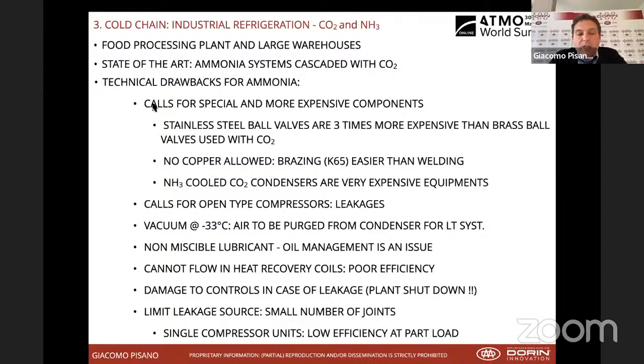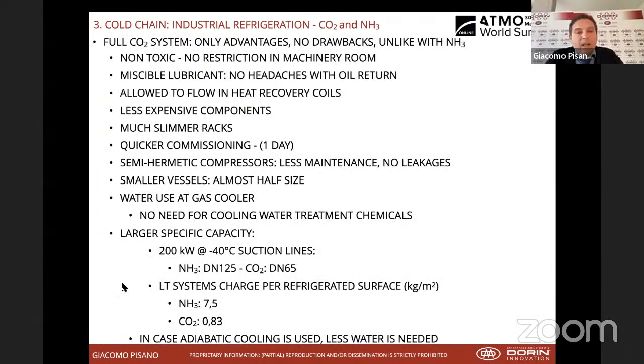During heat recovery, in most cases, ammonia cannot flow directly in heat recovery coils. So for heat recovery, CO2 may be more efficient. In case there is some leakage, you have to take care that the leakage does not affect controls. Otherwise, the plant may shut down. Clearly, in order to decrease the number of leakage sources, you have to try to bring in the smallest number of joints possible. So this brings about single compressor units that are normally less efficient during part load. From a CO2 standpoint, clearly CO2 is non-toxic in the classical sense, but specific measures have to be in place to take care of the fact that CO2 interacts with our breathing. CO2 works with miscible lubricant, so oil return is definitely easier.